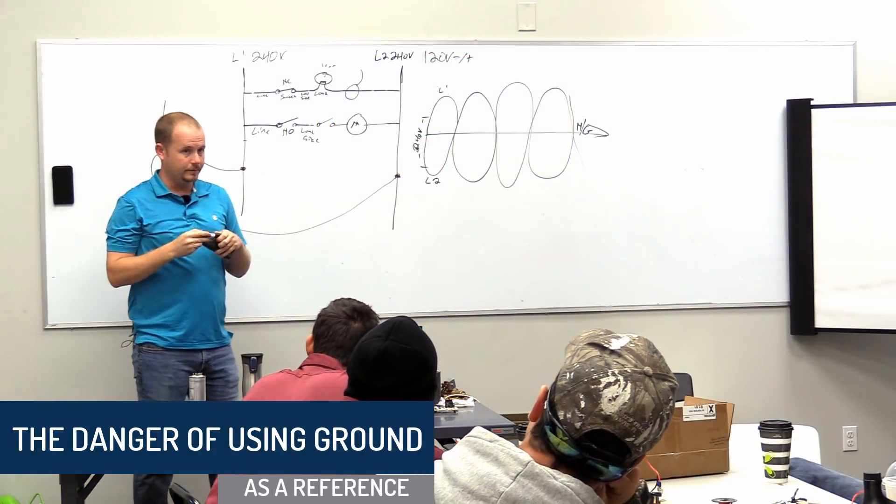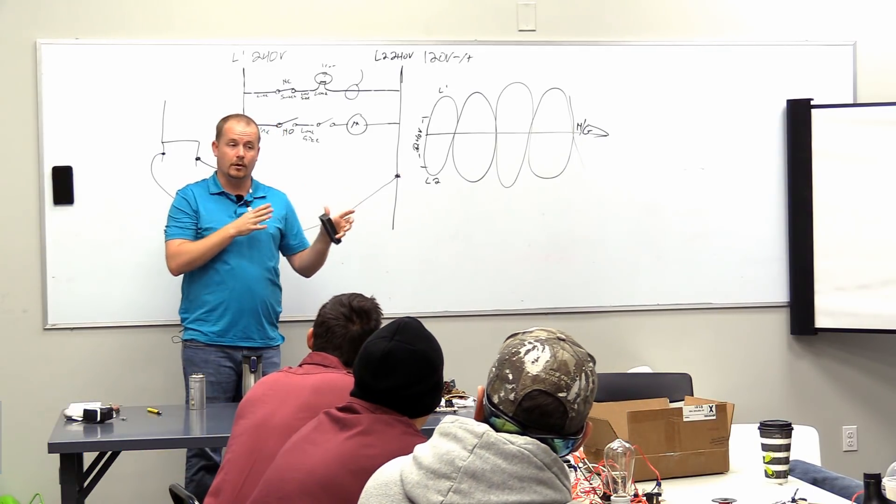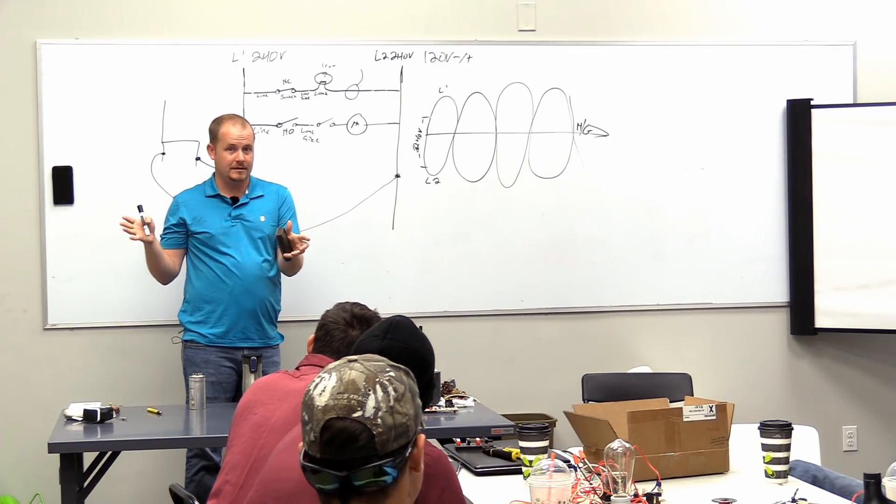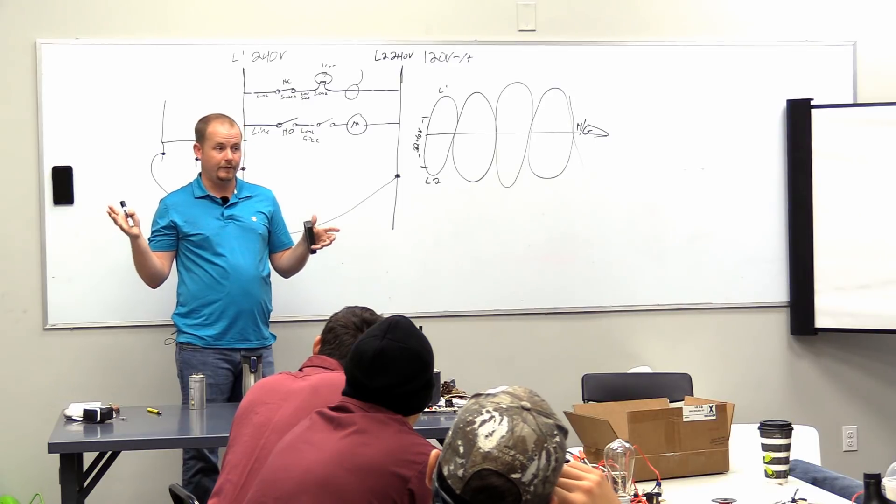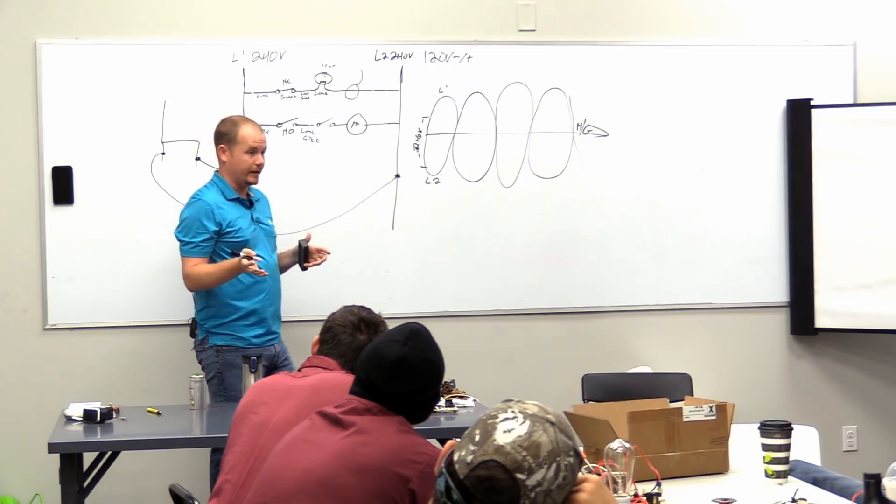Now does a 240 volt circuit have a neutral? Does it? No. Now are there some 240 volt appliances that do have a neutral? What's an example of one? Dryer, range. They will have a neutral and that's because there are certain 120 volt components in it, right?